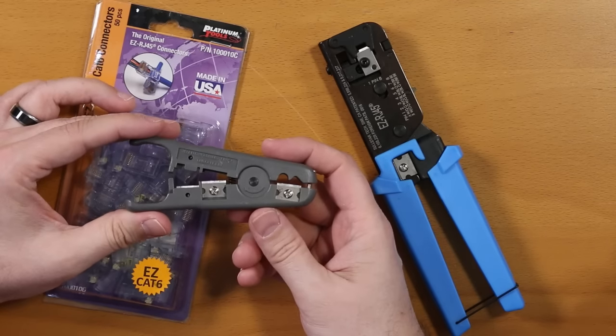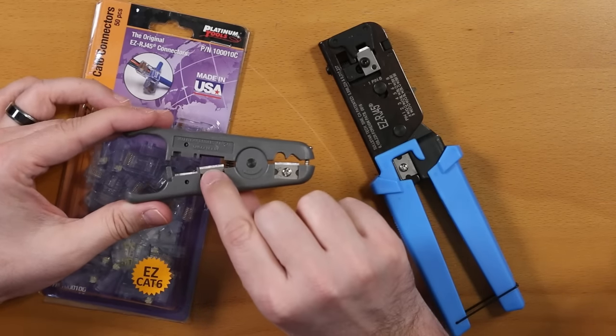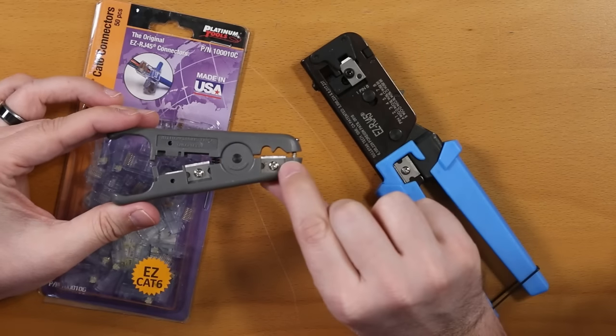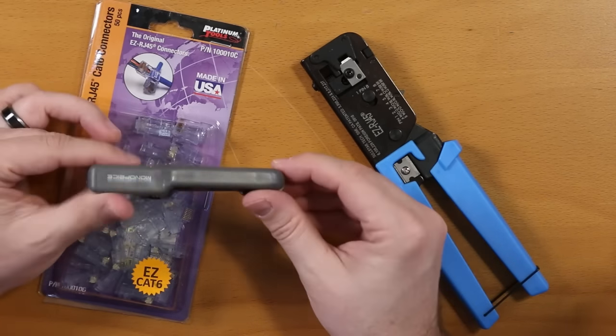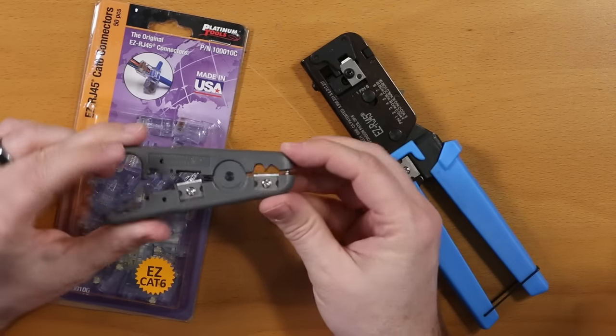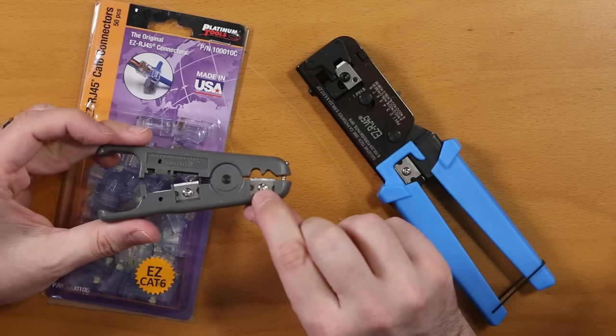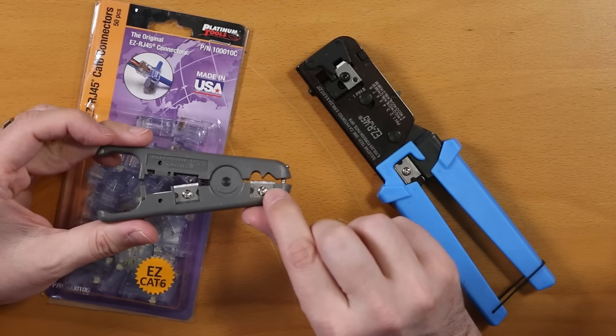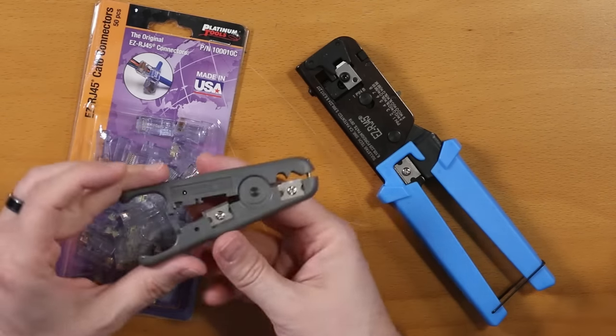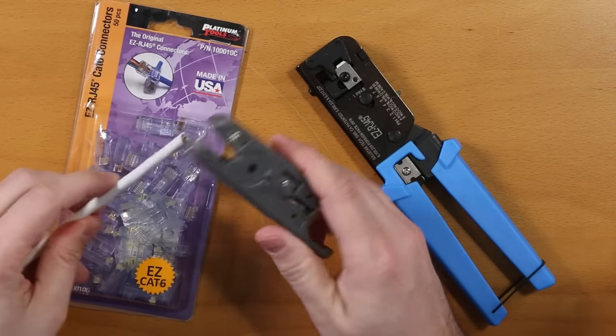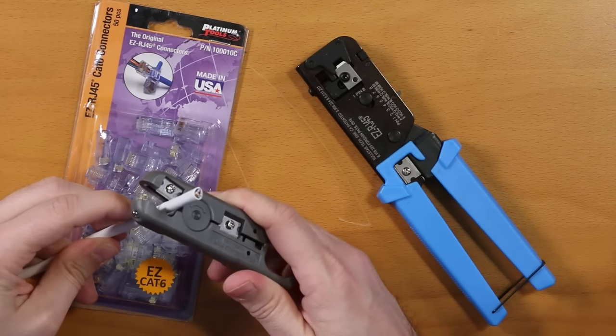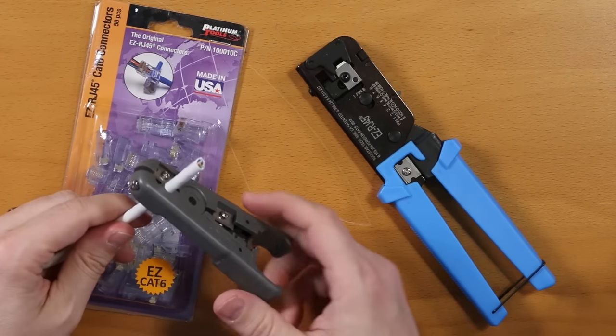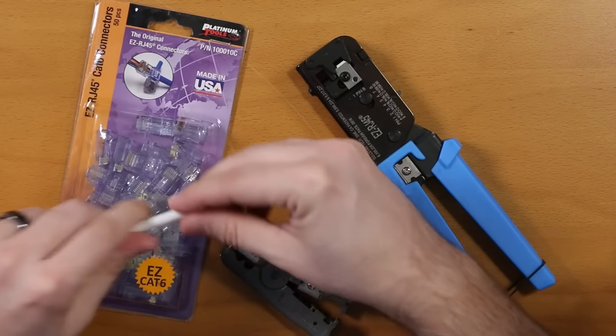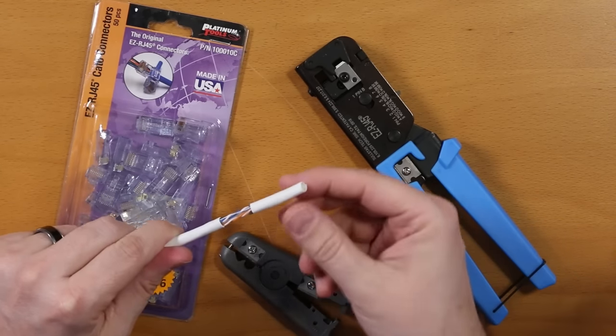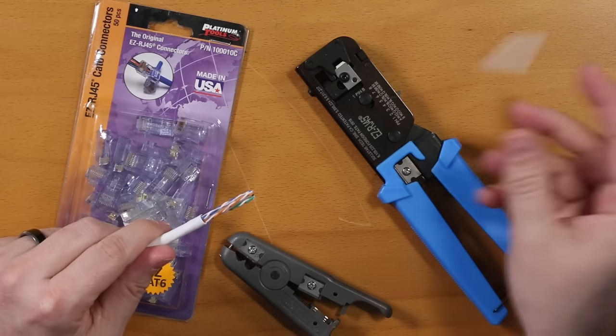So the reason that I like this tool is, first of all, you have just a way to cut cables off right here. But up here in the front, we have an adjustable, so there's a screw here. This allows you to adjust how deep these two channels cut. So depending on the thickness of your cable, essentially you just stick it in here and you clamp it on where you want, and you basically just twirl it around a couple times and take it off, and then the jacket slides right off just like that. So it works really, really easily.